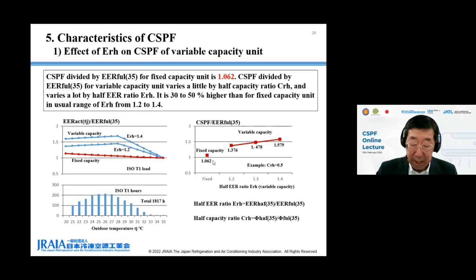Cspf divided by 35 degrees C full EER of variable capacity unit increases when half EER ratio ERH increases and varies from 1.376 to 1.579 in usual range of half EER ratio from 1.2 to 1.4. Cspf for variable capacity unit is 30 to 50% higher than for fixed capacity unit. Next, please.